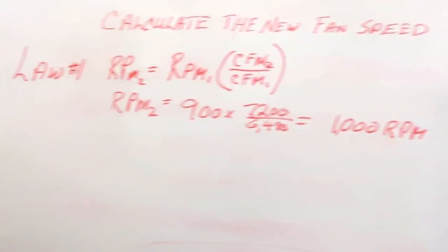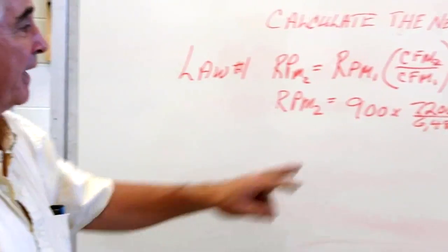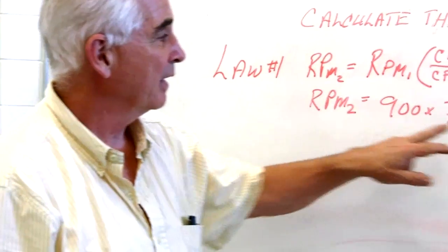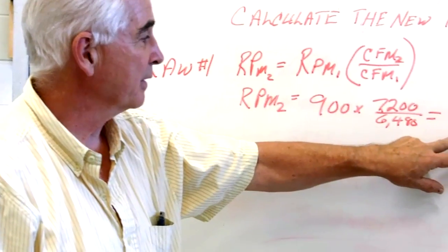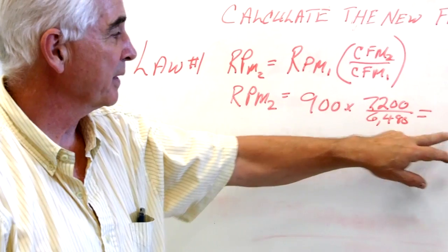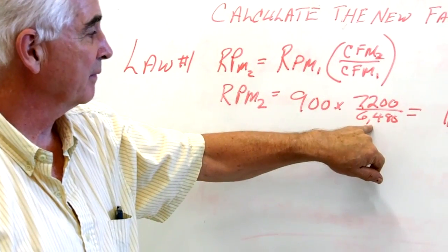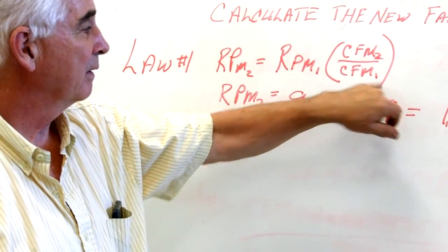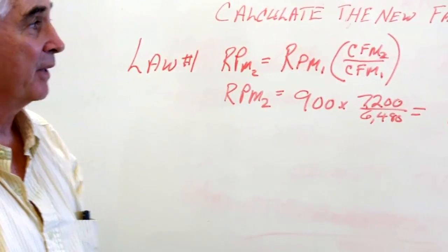So if we increase the fan speed from 900 to 1,000 RPM, we'll increase the CFM from 6,480 to 7,200.